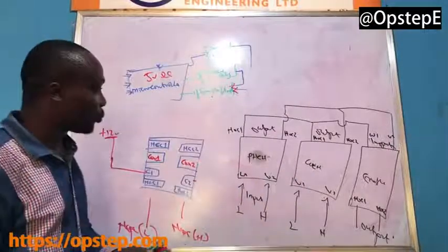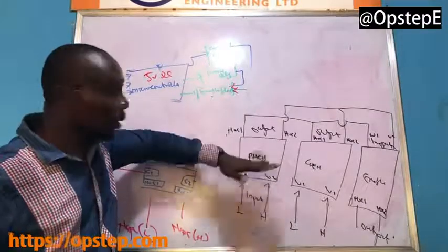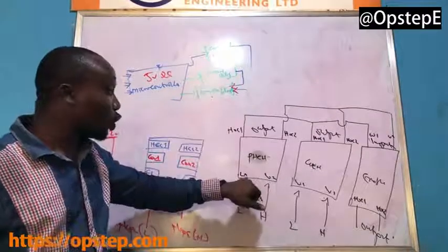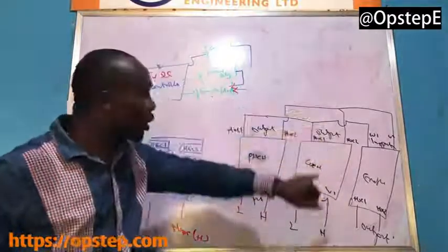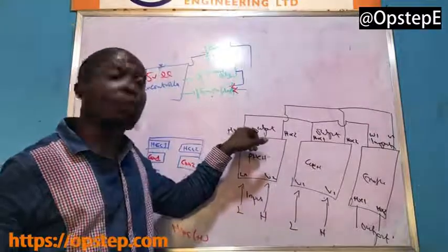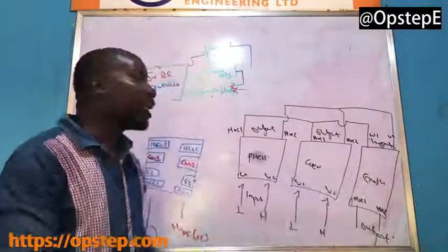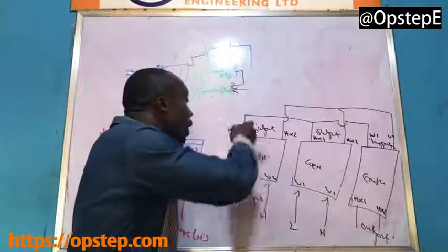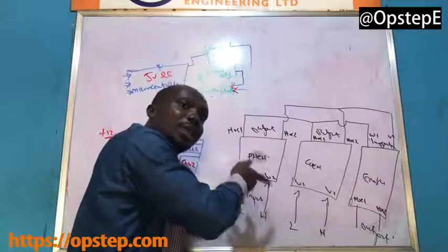So this is the issue. Assume that NEPA is available here. NEPA is on your what? Wiper 1, wiper 2. Generator is also available. Generator is on wiper 1 and wiper 2. But you are going to choose to pick what? Normally open contact 1, normally open contact 2. It is the one that you now energize. The coil that you energize is the one that will switch.